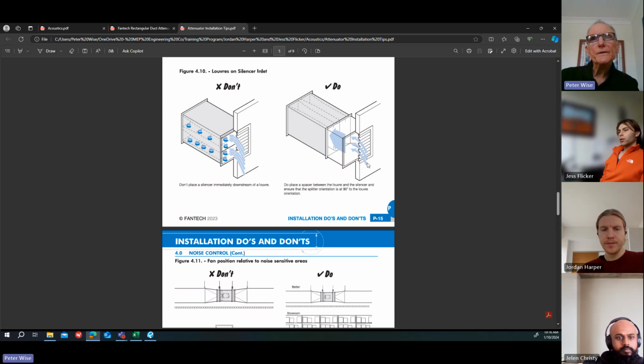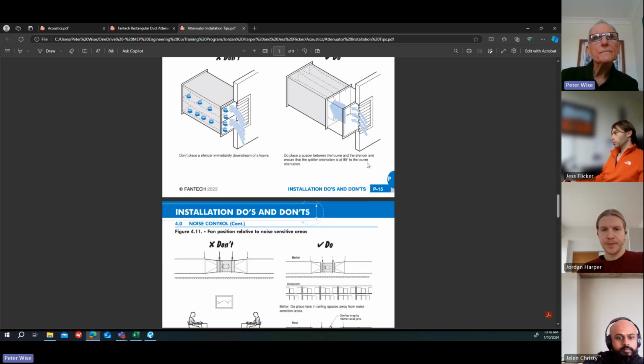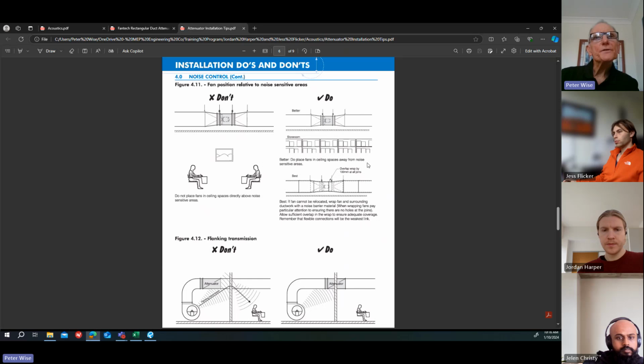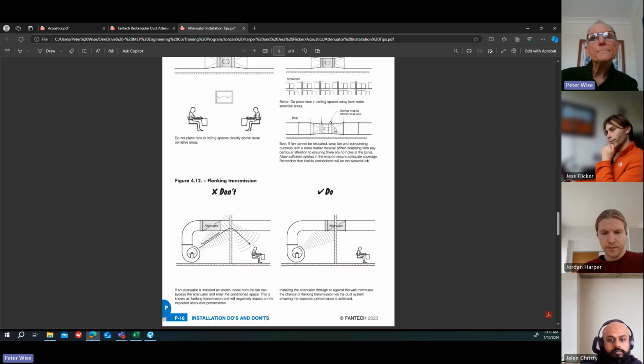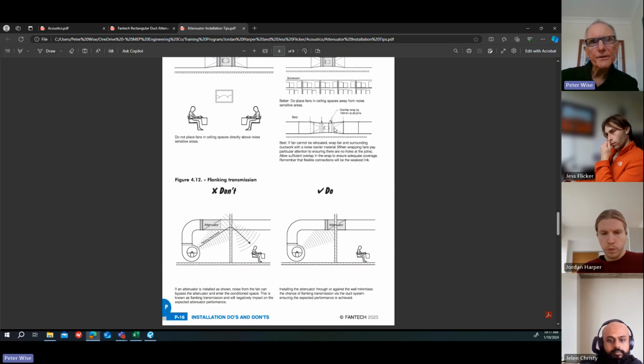Same sort of thing on the inlet side. Now this is another thing to take note of: fan position relative to noise sensitive areas. So if you can, don't put a fan or a fan coil unit directly above where people are working, or trying to have a quiet space to function in. Try and put the noise source back over a storage area or somewhere else. I mean, this is common sense again. It's not always possible, but if you can, get the noise source away.